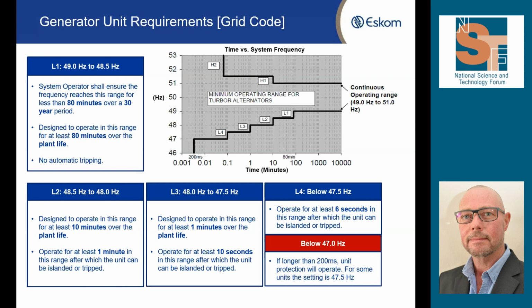As we move towards the left, when we get to the range of 49 to 48.5 hertz, there are restrictions here. Over the lifetime of a large generator, they were only expected to be able to tolerate those types of frequencies for about 80 minutes. The lifetime of the generator is typically around 30 years. So you can see that there are quite strict tolerances already as we move from just 49 hertz down to 48.5.